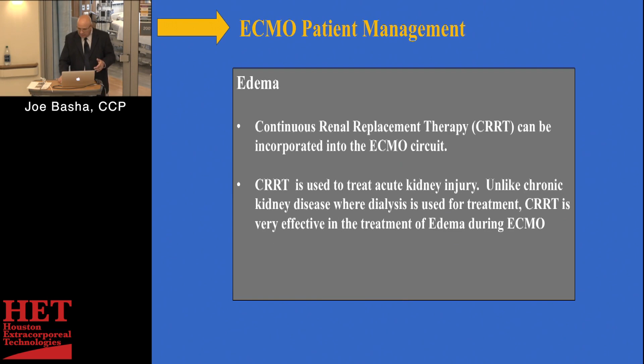Some machines are better than others at handling the hostile environment of the CRRT circuit. The pressure on the access line is going to be in the negative 80 range. The pressure on the positive side is going to be between 200 and 280 millimeters of mercury, and most of the technology that exists has a hard time managing that because it's designed for a Mahurkar catheter and totally different pressures.